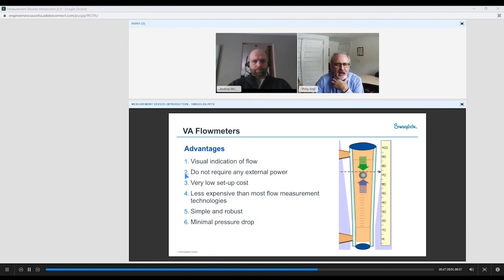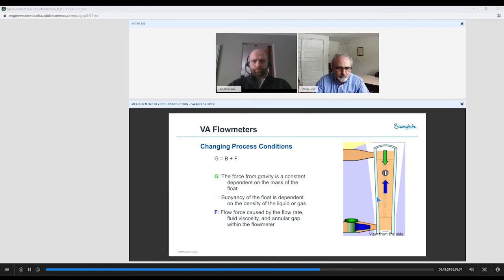Beautiful thing here, it does not require external power. Very low setup costs. You buy it, you install it, it gives you a visual indication. Not a lot of moving parts in here. Less expensive than most flow measurement technologies. It's very simple, very robust, and again, minimal pressure drop across a variable area flow meter. So let's talk a little bit more about how they work.